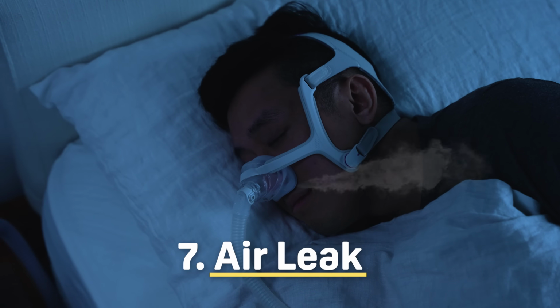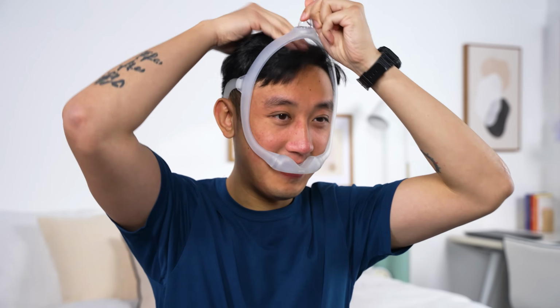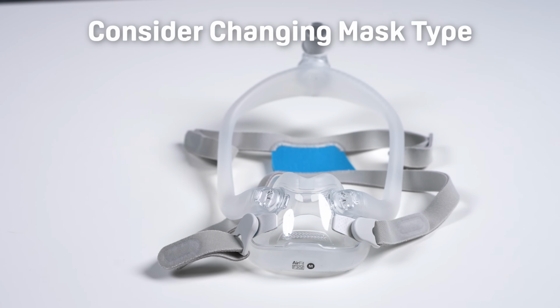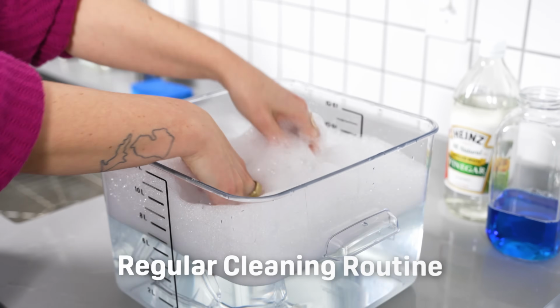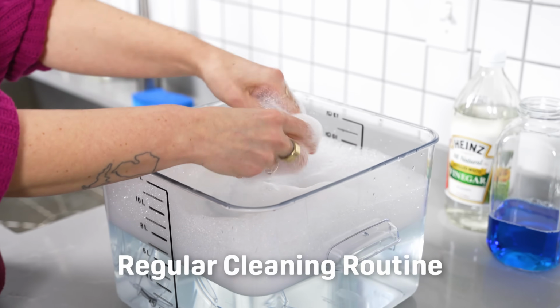The next issue I want to address is air leak from the mask. This is very common with CPAP masks, and everyone will experience air leak at some point. Oftentimes, air leak is also related to a dirty mask or a mask that is too old or fits poorly. So take care to fit your mask appropriately, and you may decide to switch your mask type if you need a better fit. Again, a regular cleaning routine will help remove all those old skin cells and dirt and debris from the surface of your mask, which cuts back on air leak because then it will create a better seal.